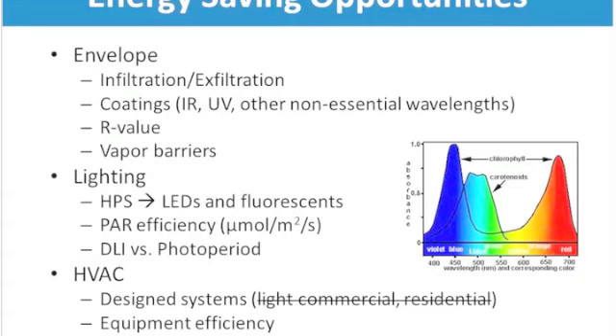Having an HVAC system designed with good efficiency, but also think about economizers, specifically an air side economizer. I know a lot of you are nervous about bringing outside air into your space due to pest control concerns, or letting carbon dioxide out once you've enriched the space. But there's a lot of energy savings potential with economizers, and in some jurisdictions, if you have a space requiring 2,000 CFM of air or more, you might be required to install equipment with an economizer.